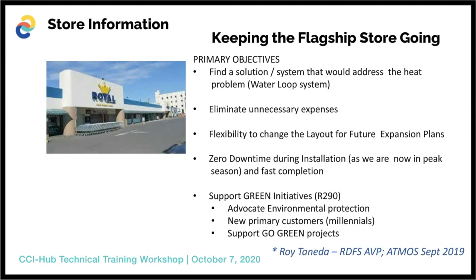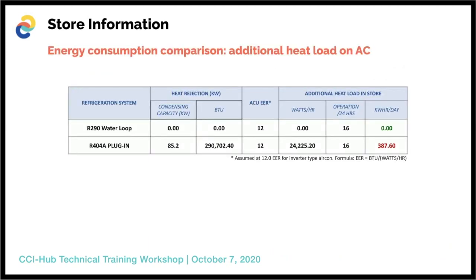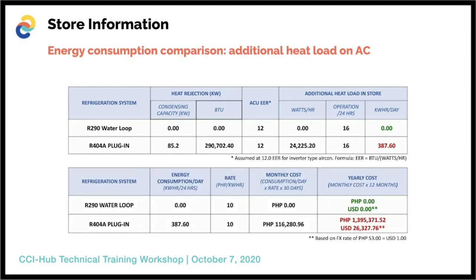If you look now at the next page, here you can see the benefits of a water loop system as opposed to that of a plug-in system, as there's no heat emitted into the store. Because of the high energy cost, this translates to savings of approximately $25,000 a year, and less cooling needed for the store due to the reduced amount of heat that is eliminated.